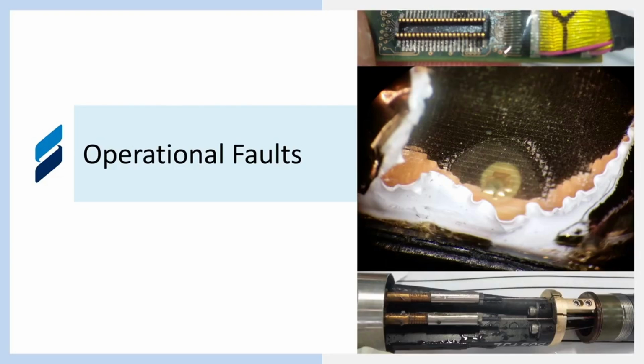Okay, now we're going to move on to some operational faults. So, these are kind of the things that you're going to see that are failures of a transducer, maybe caused by some of the faults that you saw earlier, but these are actually manifesting on the ultrasound system itself. And so, they're two very related things. Sometimes independent, sometimes you can have a fault that doesn't result in image quality issues. But these operational faults that really impact functionality and image quality of the transducer absolutely are tied to some sort of failure or physical failure of the equipment.